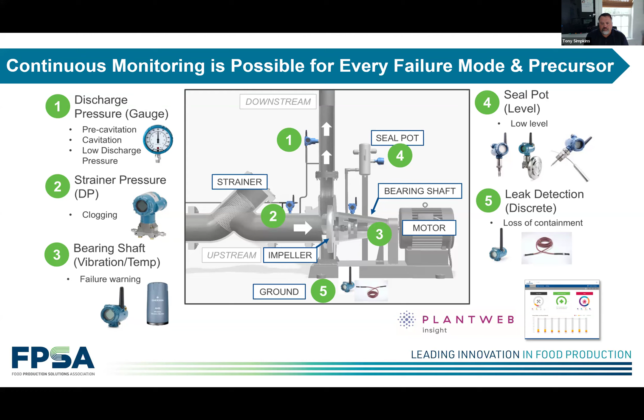So let's go to an example. In this example, this gives you the idea of not only what you can monitor, as we saw on the previous slide, but also what kind of real world dollars and benefits this can bring. Obviously, you see the challenges here: pump shutdowns causing reduced production, maintenance expenditures over budget, insufficient data. And that online pump monitoring solution gives you an early warning system that doesn't necessarily need a machinery expert to interpret. You're going to be able to get such indications as pump vibration, cavitation, bearing temperature, strainer plugging, seal leaks, and eliminates those nuisance alarms that many times come with not knowing exactly what's going on in the asset.